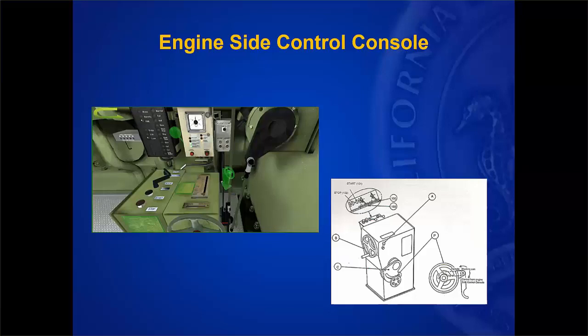On the changeover, it's important that you specifically mechanically disconnect the hand wheel. There is a wheel on the front of this local control, and when you turn that wheel, you are actually moving the rack assembly directly - there's no interface, you're mechanically moving the rack. As part of the changeover process, you have to disconnect that manual connection and switch it so that the governor will control the rack.